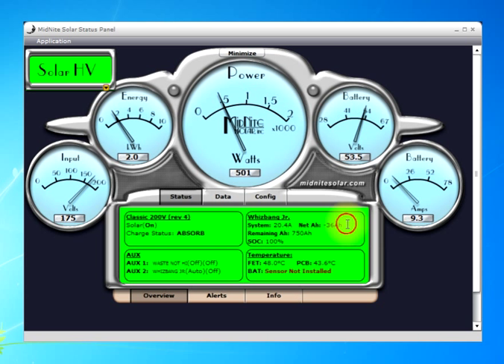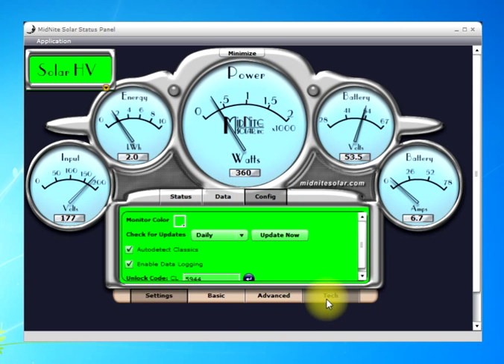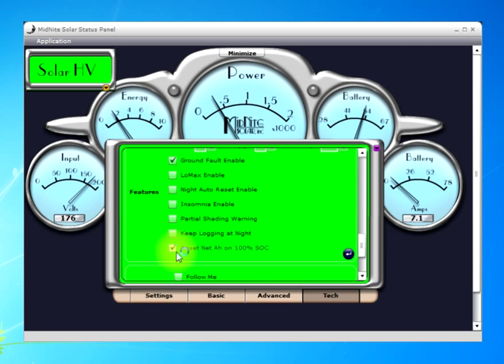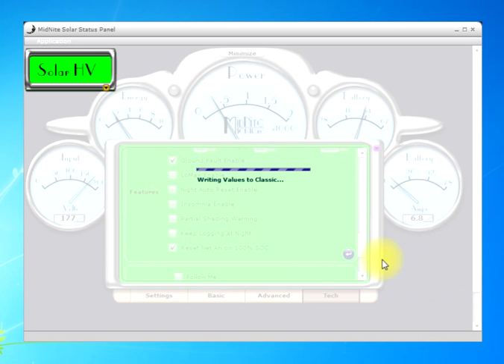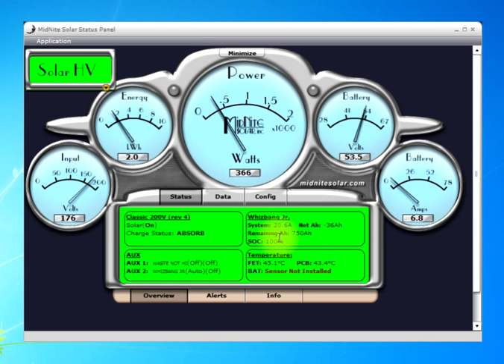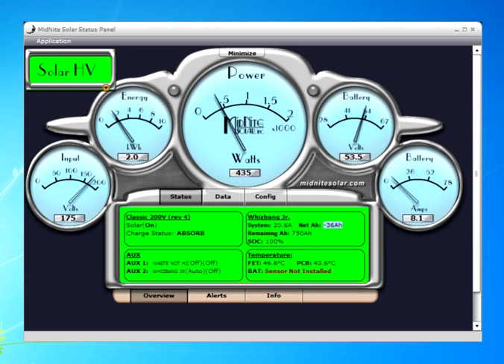Net amp hours will reset when it goes to float — or you can set it either way. To have it reset every time it goes to float, go into the Config tab, then the Tech tab, and tick the box that says 'reset net amp hours on 100% state of charge.' When the controller switches from absorb to float — which triggers 100% state of charge — assuming the controller is programmed correctly so the batteries are truly full, it resets to 100% state of charge and the net amp hours reset to zero. That concludes setting up the Classic Lite, or a regular Classic, using the local app for the Whizbang Jr. Thank you.